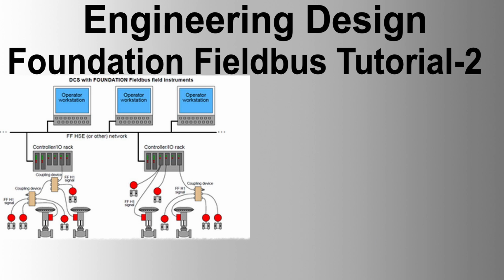Tag location, device tag, and function block. Tags are useful for humans but need longer data for communication. SMKP provides services to replace device tag and block tag with node address and index to simplify further communications. This mechanism ensures that devices and function blocks can be accurately and efficiently located within the network, facilitating smooth operations and management.